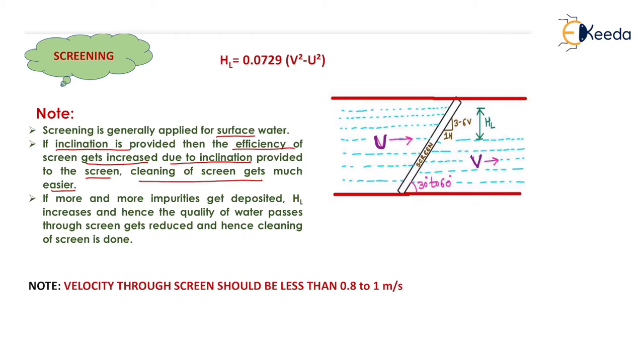What will happen if more and more impurity comes into the water and chokes the screen? The level of water before the screen will increase, and after the screen, the level of water will decrease. The head loss value will keep increasing. As more impurity deposits, head loss (HL) increases, which means the quality of water passing through the screen gets reduced, and hence cleaning of the screen is done. HL will indicate that the cleaning time has been reached, and we need to clean the screen before using it for further purification.